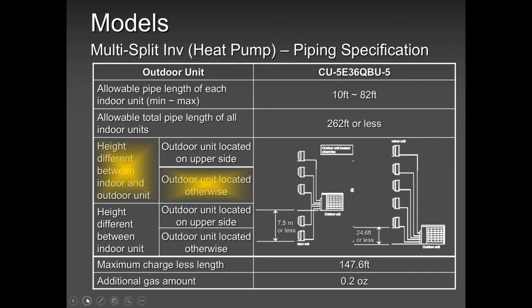Always, guys, I always try to remind my guys, always try to give less stress to this outer unit. Try your best to give less stress to this outer unit. When I say less stress, I mean try to place this outer unit in a location where the distance between the indoor and outdoor is not far away. Okay, guys? Please remember, even though this outer unit is good for 82 feet per indoor unit, if you have a choice, keep them closer. Okay? By keeping them closer, you give the compressor breathing space, not to work too hard. And when it doesn't work too hard, it will last you longer and longer and longer.